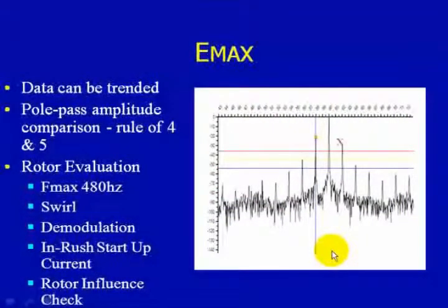Now, PDMA, as you can see here with our Emax, uses a spectral analysis approach, and spectral analysis allows us to take a simple current signal and apply a FFT or fast Fourier transform algorithm. FFT capability reveals small but very informative frequencies like pole pass frequency.